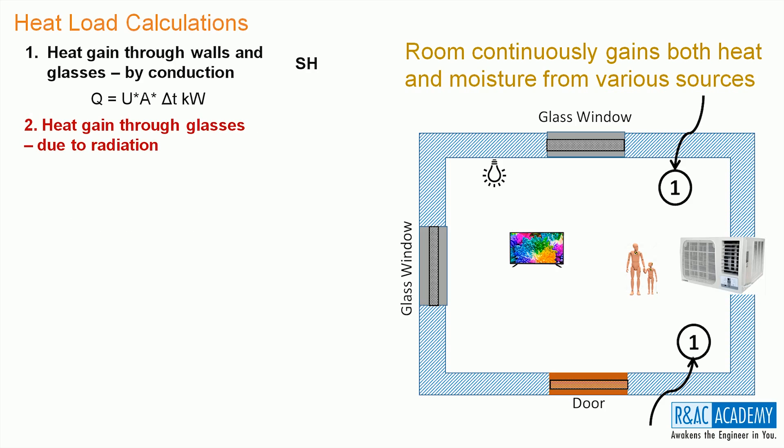The next source is heat gained through glasses due to radiation. This is the heat that flows from outside into the room through the glasses. This heat transfer happens by radiation. Only energy transfer happens in this case also. Hence, room gains only sensible heat. This is computed using this expression: Q equals area times solar heat gain per unit area. The solar heat gain per unit area can be had from the data tables.